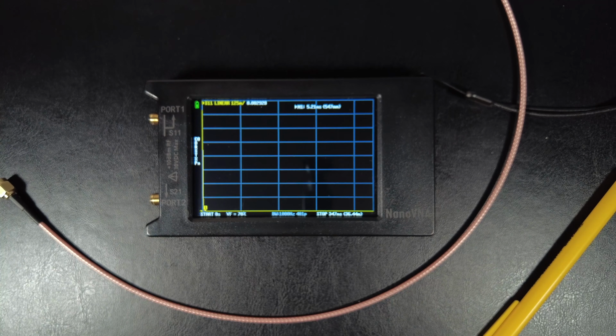Now this test is another S11 test, so you just need to do the open, short, and load part of the calibration. The steps are: first, measure the length of the cable. Now I'm using this shorter piece of cable because it'll be a lot easier to demonstrate. This cable is actually 547 millimeters long.